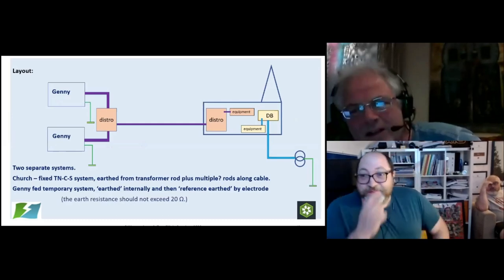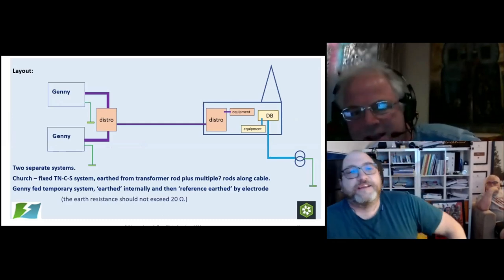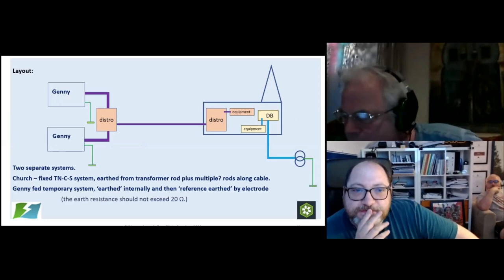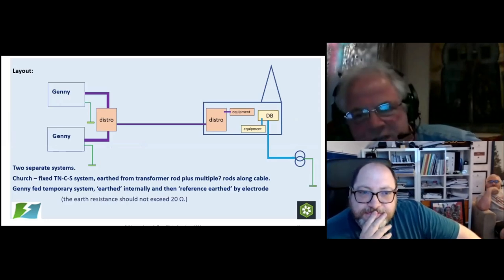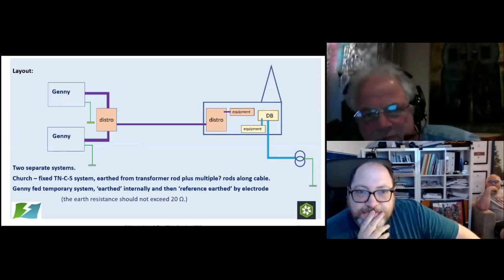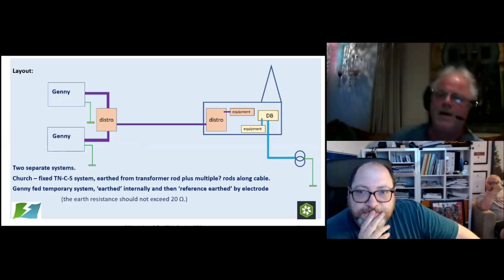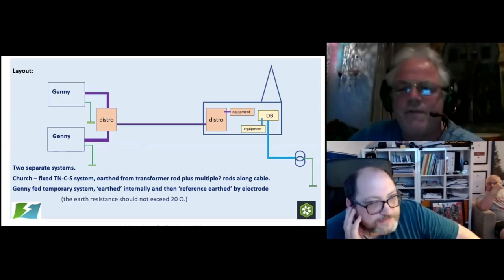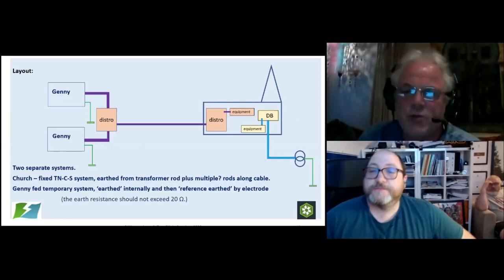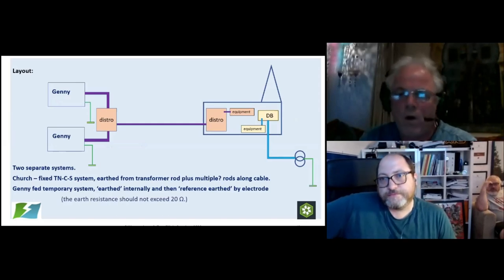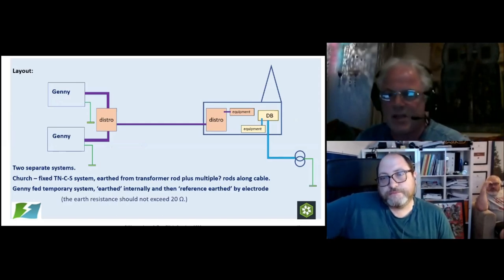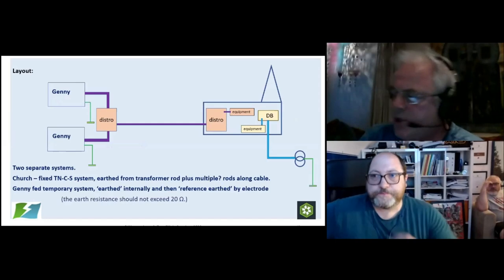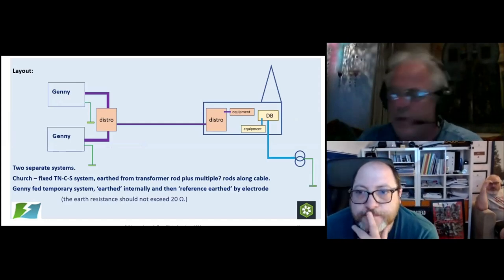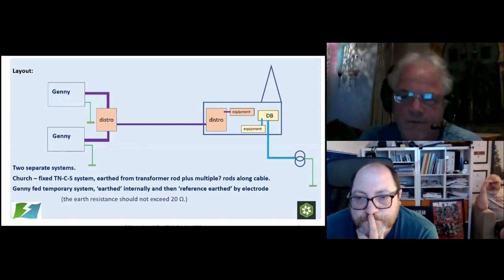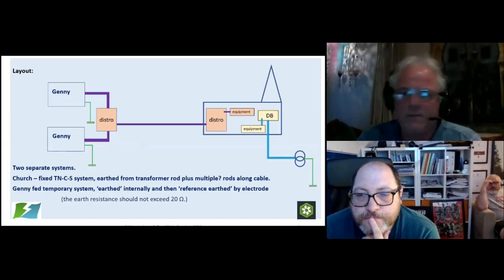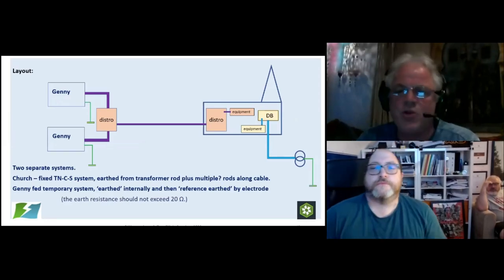So I've actually done this slide, looking at the layout that he's mentioning. Here we've got the two gennies, the twin set gennies, which are obviously synchronized, feeding a distro. And then from that distro, we're feeding into a distro inside the church, which is feeding the supplies for the concert, the lighting and everything else. Inside the church, there is a TNCS system with its own distribution board feeding the equipment that is normally inside the church.